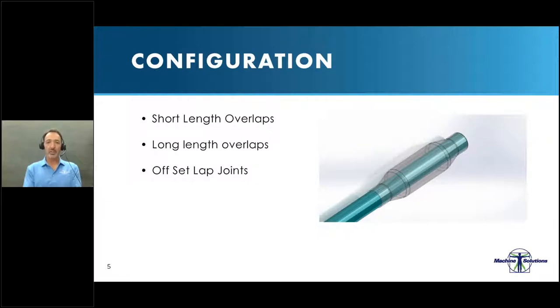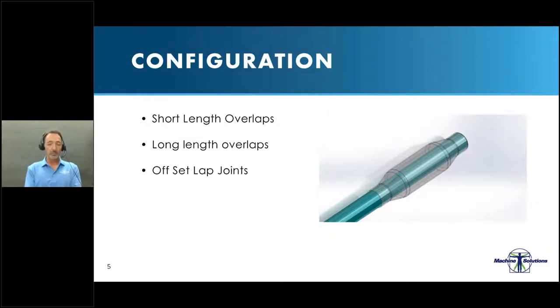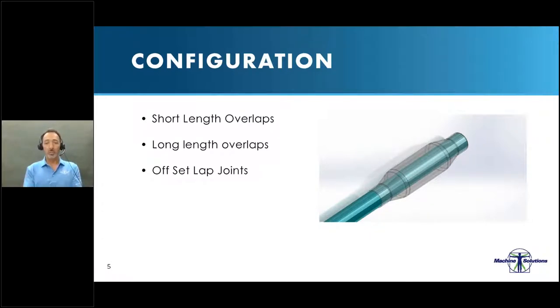The different configurations are pretty simple: a balloon to a tube in which either one leg or both are adhered to the shaft within. These can be similar or dissimilar polymers. In the case of similar polymers such as PVC or urethane, if both the balloon and the shaft are the same, you are welding them together. In the case of dissimilar materials such as PET to PEBAX, you're creating an adherence between them. These overlaps can be long or short in length — it all depends on the requirements of that joint in terms of strength and pressure resistance.